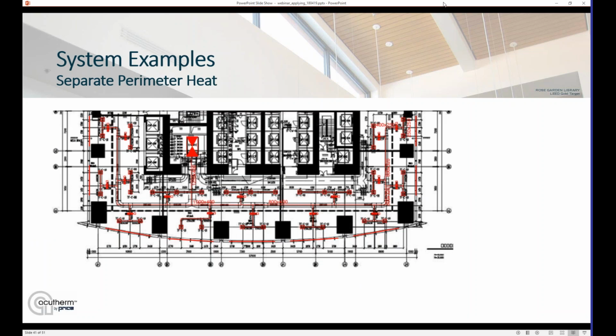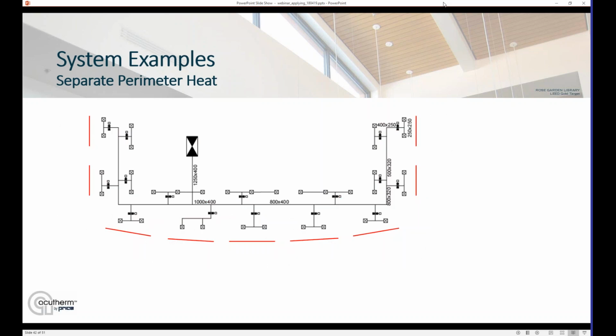Here's an example of a separate perimeter heat system, and I realize that drawing's a little hard to see, so let me eliminate a bunch of it. It was originally laid out as a VAV box project, and we converted that to an all low pressure Therma-Fuser diffuser approach. In this particular instance, though, with the separate perimeter heat taking care of the skin losses, we can approach this just as a cooling only zone, or if you need morning warm up, that works too in this approach.